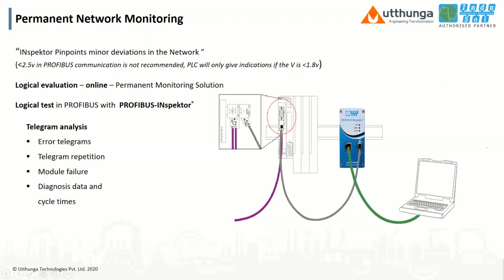Here you can see we have connected the inspector to the D9 female port, and we can access the inspector through the LAN connection. It is 24 hours monitoring, and it will give detailed information about the status of the network. You can see error telegrams, repeat telegrams, any failures in the network, or any diagnostic data. You get this type of logical information directly from the inspector, and the inspector stores the complete data.